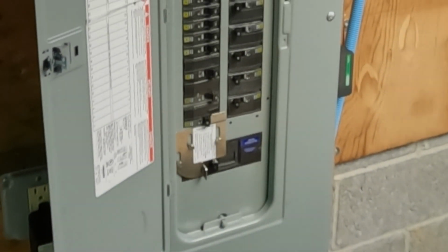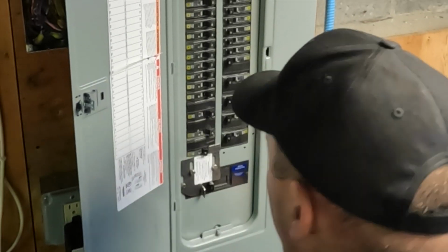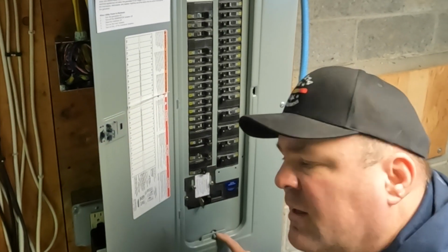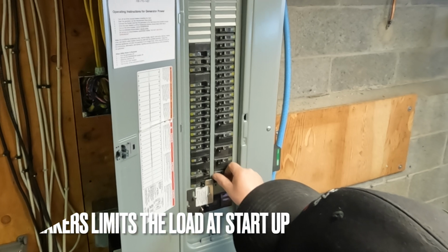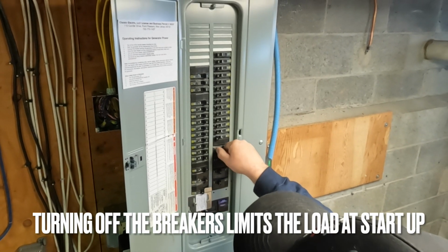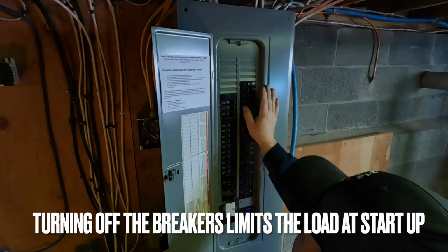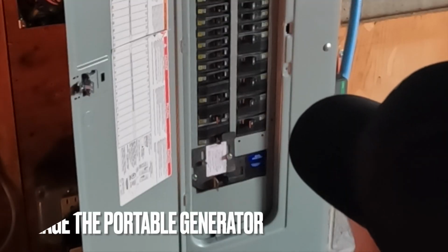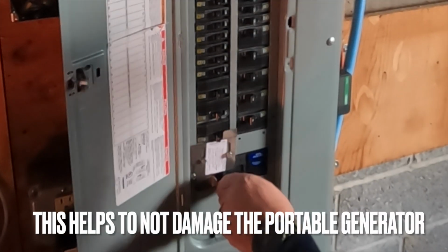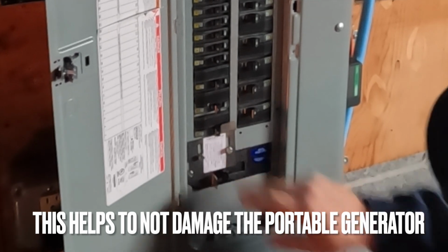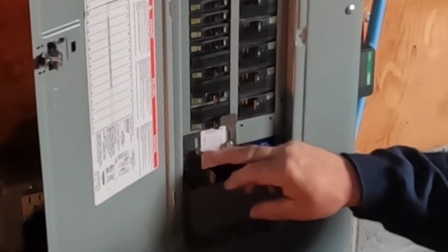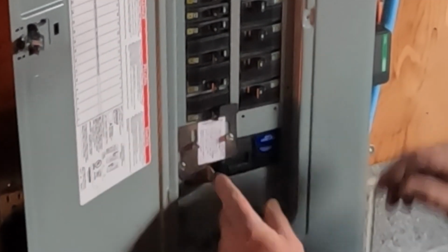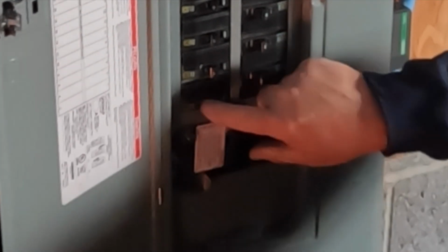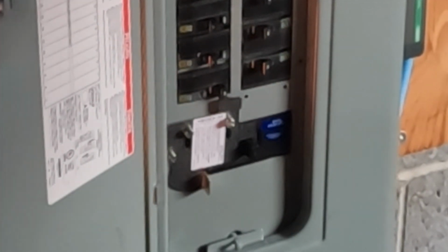You definitely want that running for a couple of minutes before you do the changeover. Okay, so now we're back down here at the panel, and the portable generator has been running for a few minutes. The next thing we want to do is turn off all of our individual circuit breakers, including the main. This is going to be really easy because we have the interlock at the bottom. As soon as I turn off this main, the interlock is going to drop down and we're allowed to now turn the generator power on.